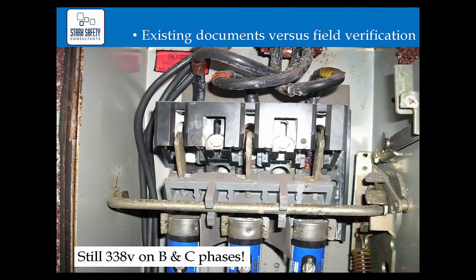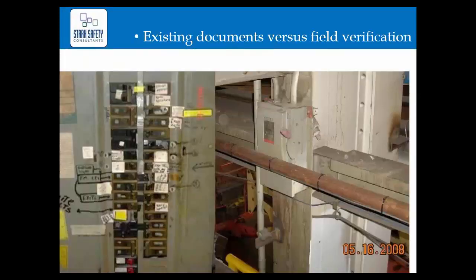Here the blades have all been opened, but the B and C phases are still energized, showing 338 volts on both phases because water has rusted in there. So field verification has many different values, and here's one case where you may find conditions that could affect not only your calculations but the actual performance of the equipment.